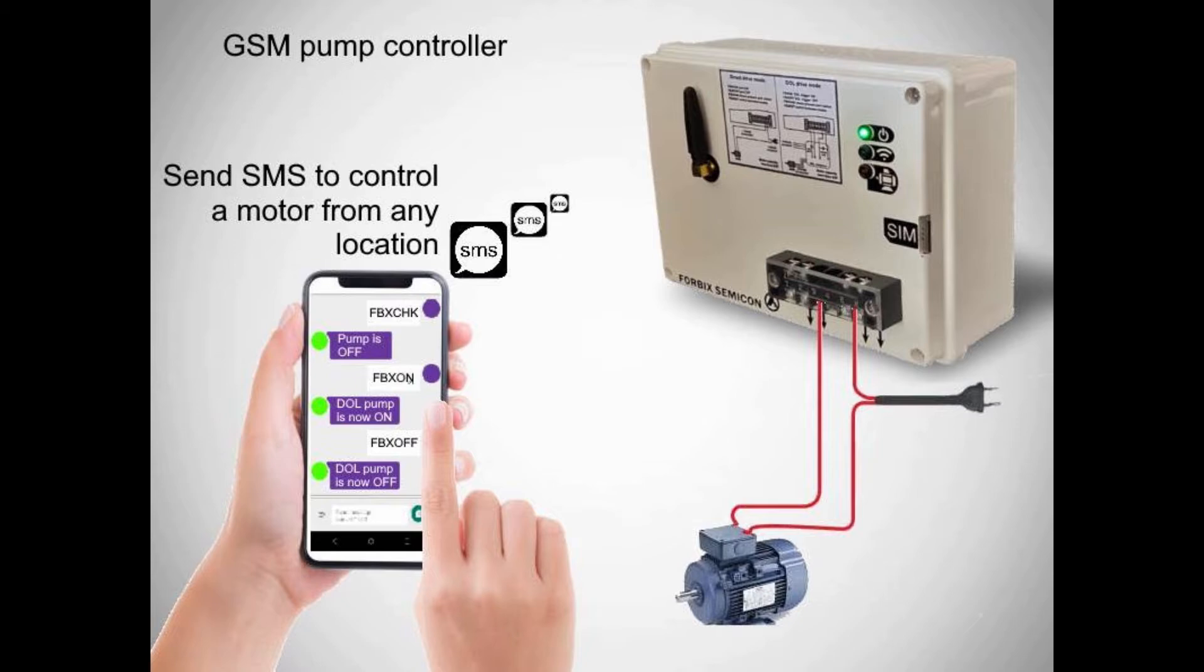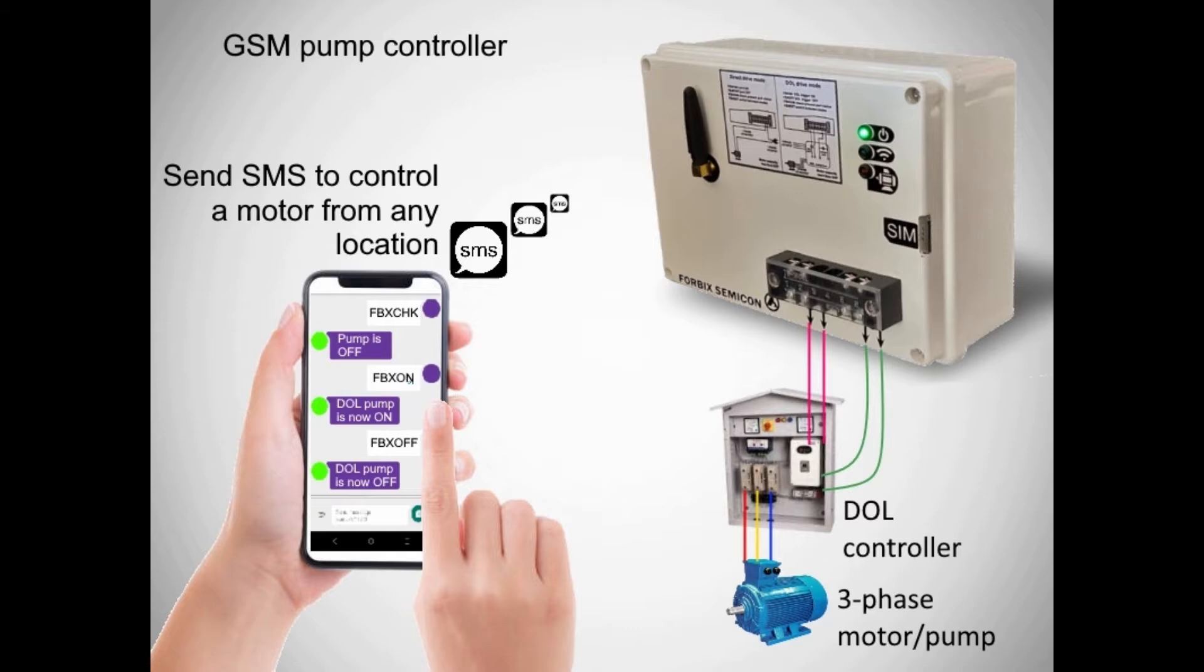The unit runs in two modes. Either it can directly drive a motor with max 15 amps capacity, or by triggering a DOL pump controller, which in turn runs a higher horsepower motor.